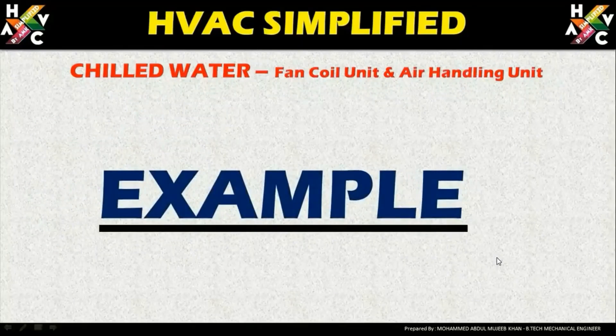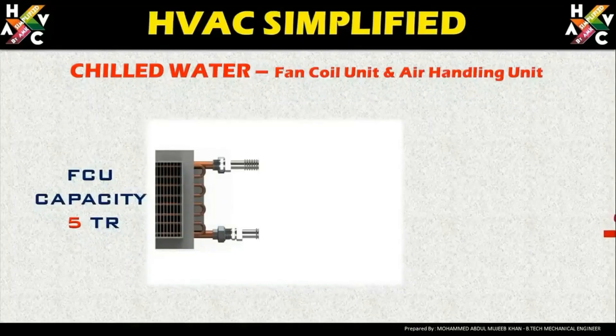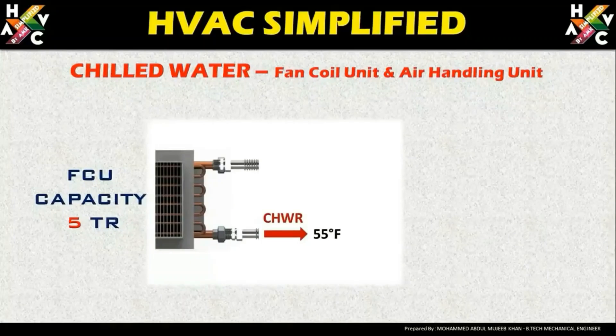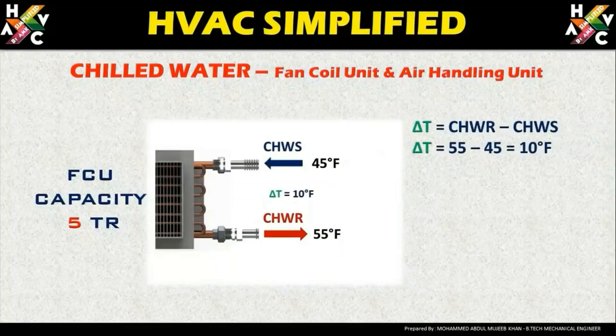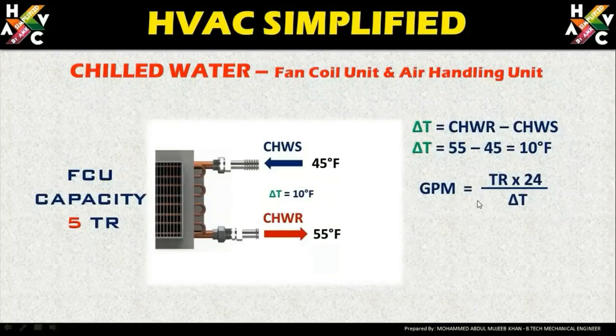Now let us understand with an example how to calculate and derive the GPM for a particular unit. Here we have taken an example of a fan coil unit with a capacity of 5 tons. For this 5-ton fan coil unit, we need to derive the required GPM. The chilled water return temperature is 55°F and the chilled water supply temperature is 45°F, giving a delta T of 10 degrees Fahrenheit.